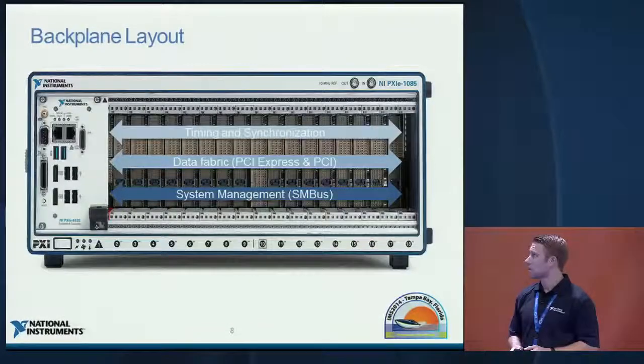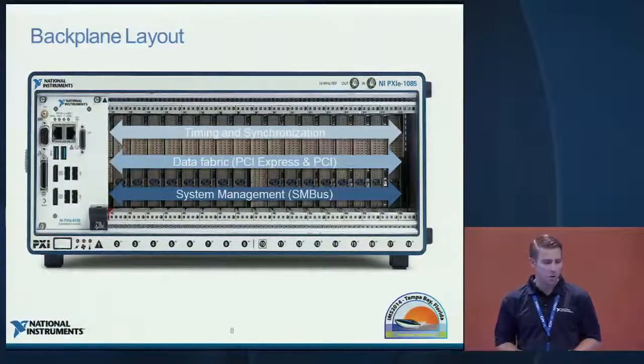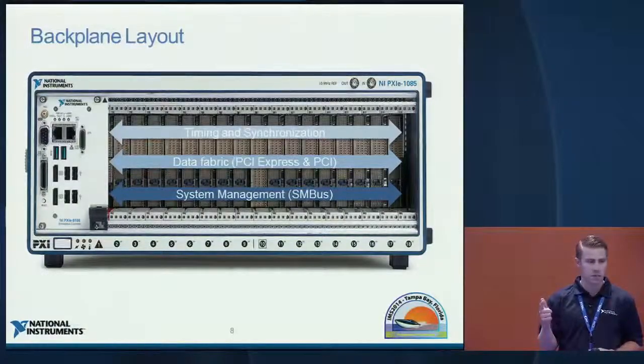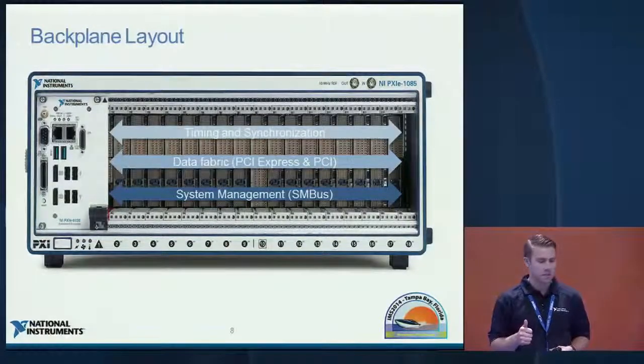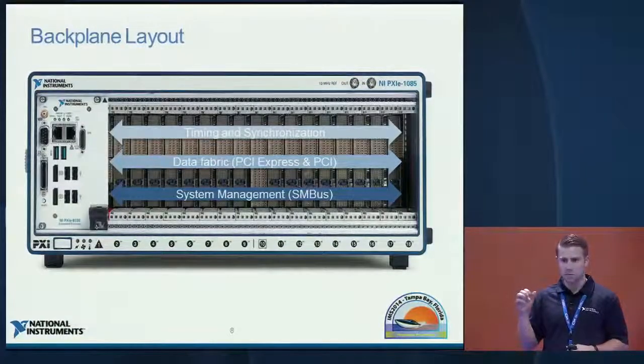The backplane itself has three main components: the timing and synchronization bus, the data fabric bus based on CompactPCI or PCI Express, and the system management bus, which is used for health monitoring of your modules — checking temperatures of individual modules and modulating fans appropriately based on the needs of your system. We'll go into the first two in more detail.